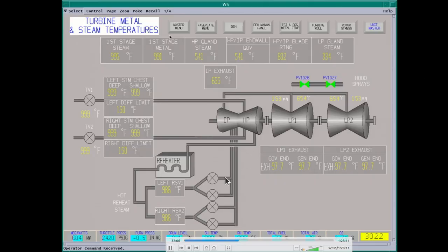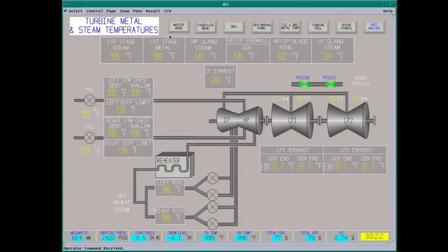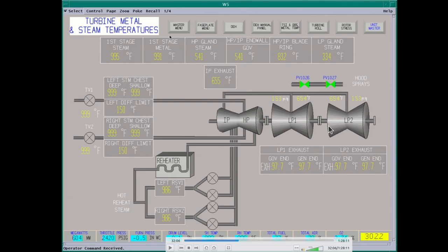These are coal flow orifice valves — they left them full open. These are the main burner shutoff valves — these are critical for safety. I kind of sped this section up as it was boring. Here's your steam turbine on the third floor. You have your IP, HP, and two LP turbines. Each one of these has their own surface condenser. There are hood sprays for low load operation and startup where you spray water to keep from overheating the last stage blading — not enough steam flow and you'll overheat the blades.